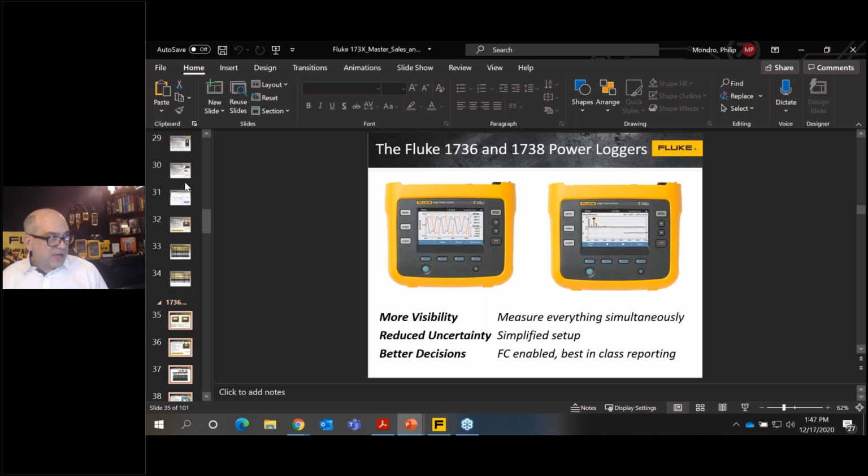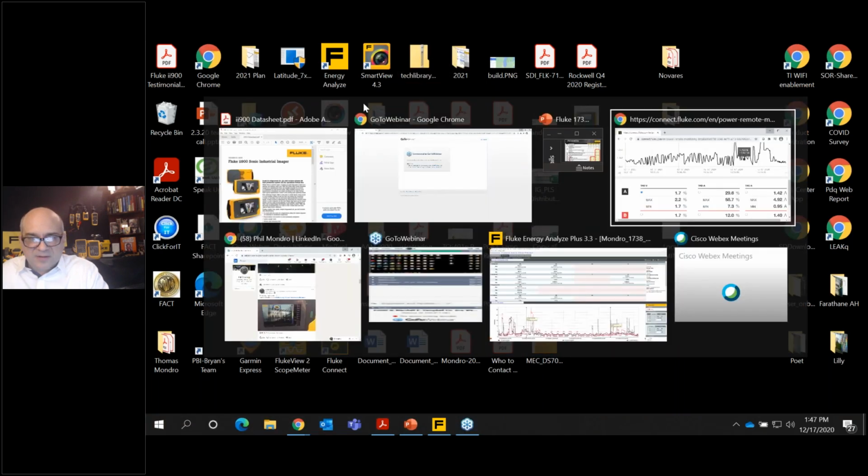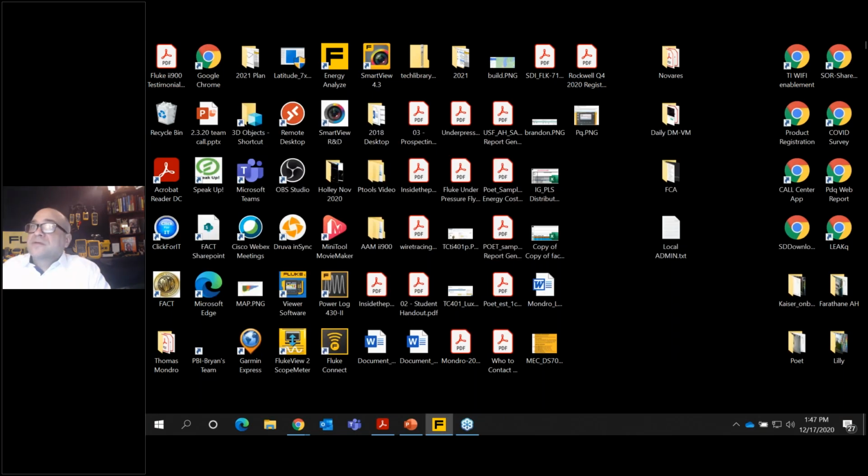So if you really want to capture a transient, and you've had some things break or electrically fail, you need to document specifically what that is. The 435, 438 would be that meter. Now let me put that guy away. I think I've got something else here to show you.